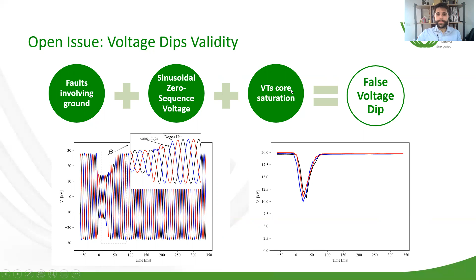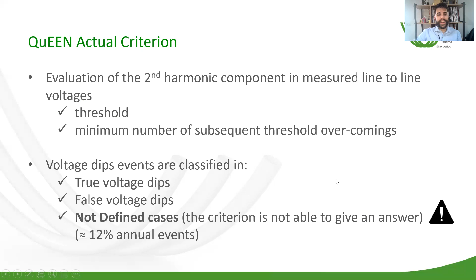So at the beginning of the QuEEN monitoring system, an algorithm, a criterion, was installed in the measurement unit. This algorithm is based on the second harmonic component measurement. For each line-to-line voltage, we measure the second harmonic. When the value of the second harmonic exceeds a threshold for a minimum number of consecutive periods, the event is recognized as a false voltage dip. But we have experienced that there is a certain number of undefined cases in which the criterion is not able to give an answer. So we have nearly 12% of annual events that are classified as not defined and so are not considered in the analysis of voltage dips.